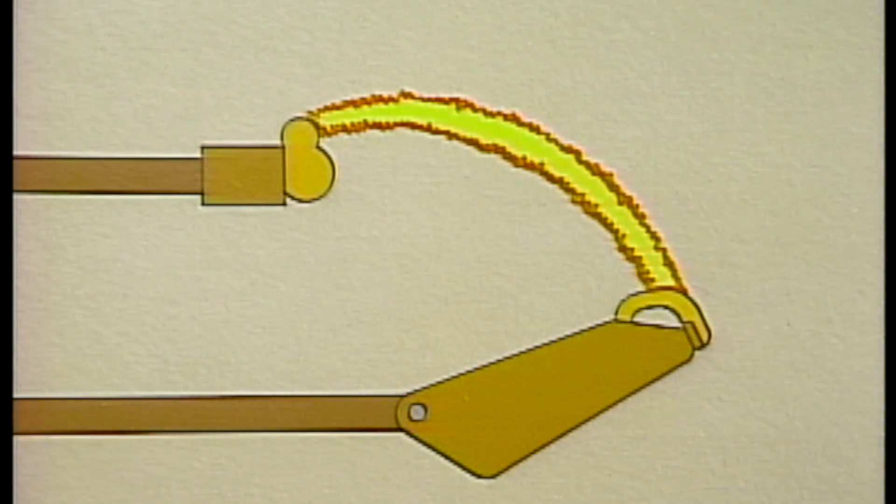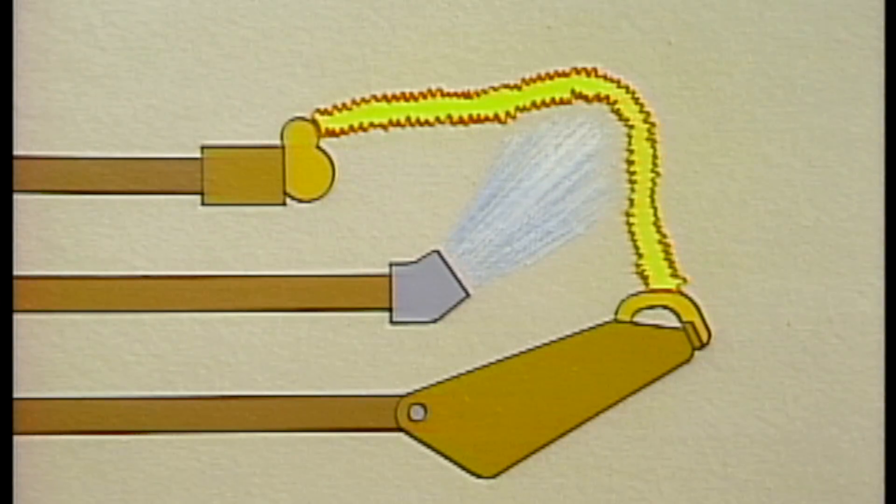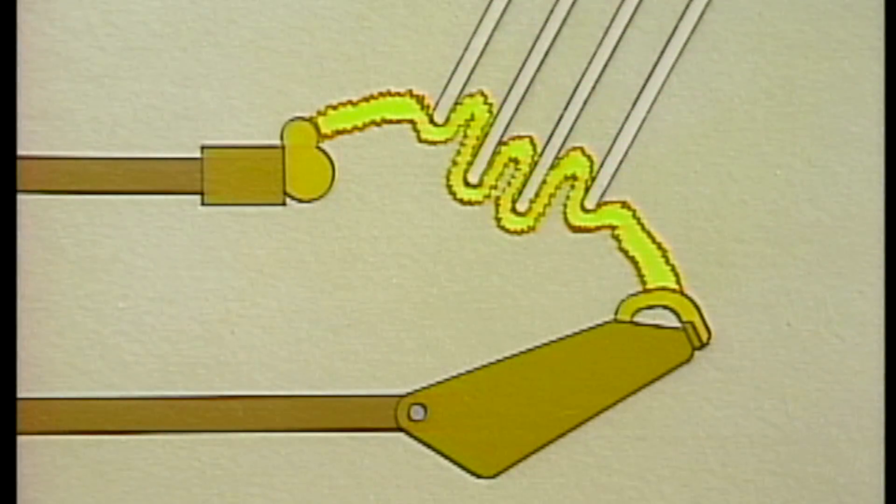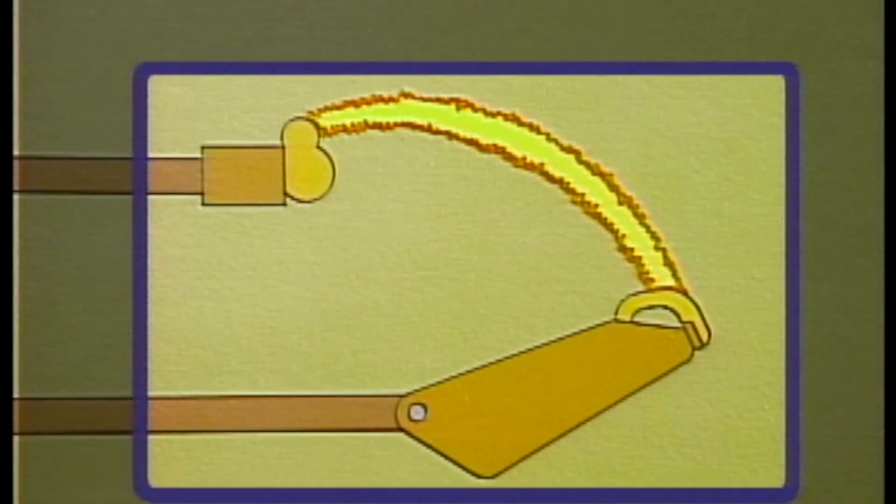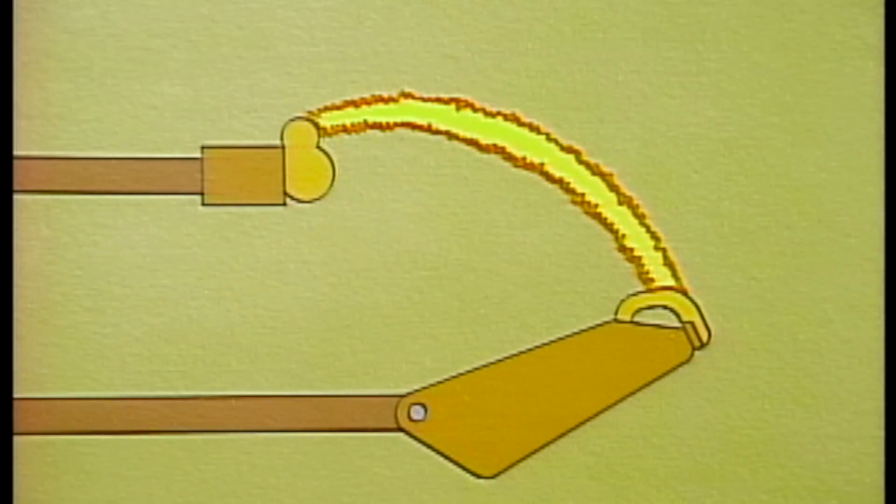Cooling refers to any physical effects that take heat away from the arc. In general, when air and gases are heated, they become electric conductors. The hotter they get, the better they conduct. So breakers are designed to take heat away from the arc. Some common ways that an arc is cooled in a breaker include directing a blast of air or gas at the arc, forcing the arc against cold metal or insulating materials which rapidly absorb and dissipate heat, and submerging the breaker contacts and the arc in insulating oil which absorbs and dissipates the heat.